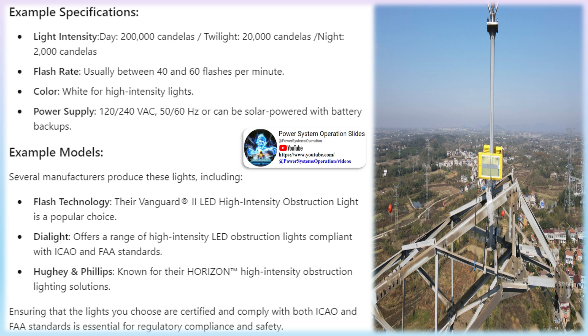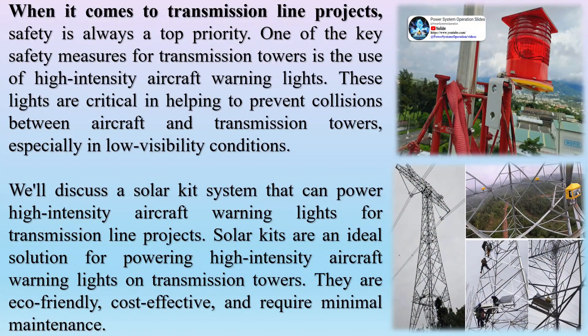Type C medium-intensity aviation obstruction light is a red constant light with an effective light intensity of 2,000 candelas ±25%. The high-intensity A-type obstruction lighting is a white flash with variable intensity during the day, dusk or dawn, and night: 200,000 candelas ±25% in daytime, 20,000 candelas ±25% at dusk or dawn, and 2,000 candelas ±25% at night. It is mainly used for buildings and facilities over 150 meters, or in conjunction with medium-intensity obstruction lights.